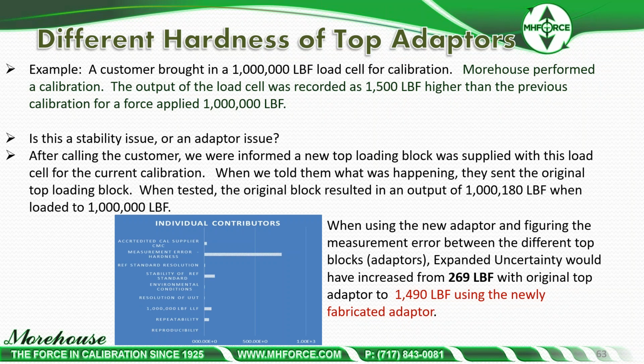When we use the new adapter and we figured our difference between the top blocks, the customer's actual expanded uncertainty would have been about 269 pounds with the original adapter. However, since they switched away from that adapter 6 months in and then sent it back in, their uncertainty went to 1,490 using the newly fabricated adapter. That is considering the difference between the deflection of those adapters.